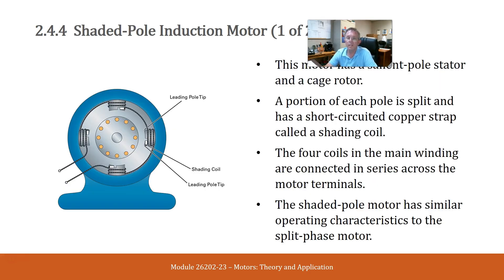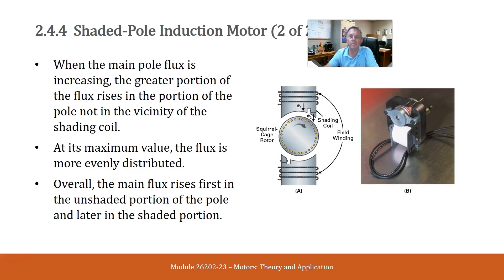Shaded pole induction motor. This motor has a salient pole stator and a cage rotor. A portion of each pole is split and has a short-circuited copper strap called a shading coil. The four coils in the main winding are connected in series across the motor terminals. The shaded pole motor has similar operating characteristics to the split phase motor. When the main pole flux is increasing, the greater portion of the flux rises in the portion of the pole not in the vicinity of the shading coil. At its maximum value, the flux is more evenly distributed. Overall, the main flux rises first in the unshaded portion of the pole and later in the shaded portion.